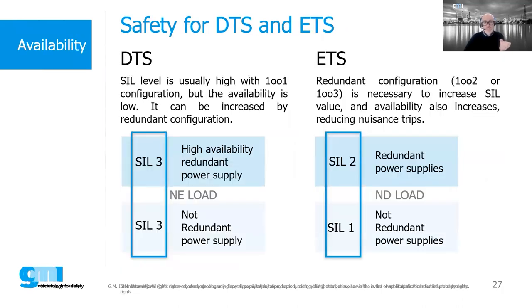Let's talk about system availability to the process. As we see from the slide on the screen, for the de-energized to safe (DTS) application, typically a normally energized load, the SIL3 level, a safety level, is easily reached through a type 1 out of 1 configuration. For this type of application, we can achieve through redundancy an increase in availability to the process. This allows us a further quality step in guaranteeing production continuity at the plant and a higher safety level.